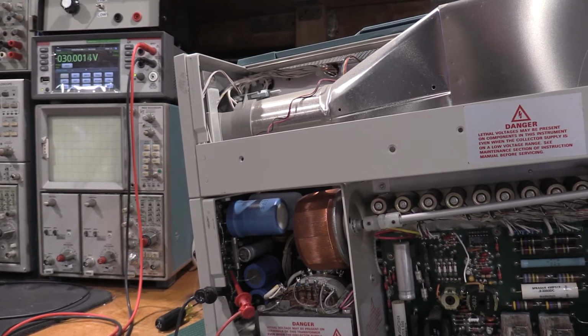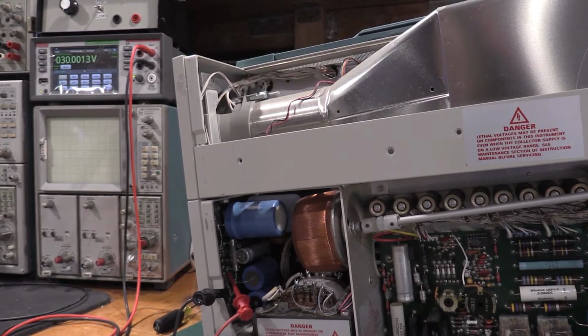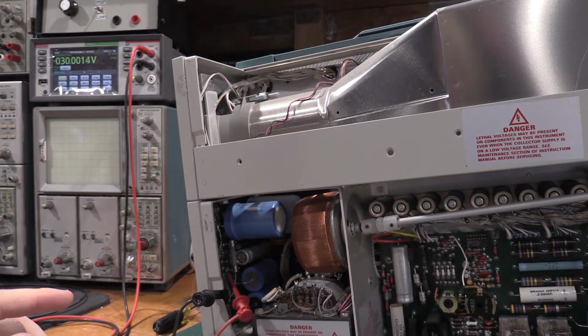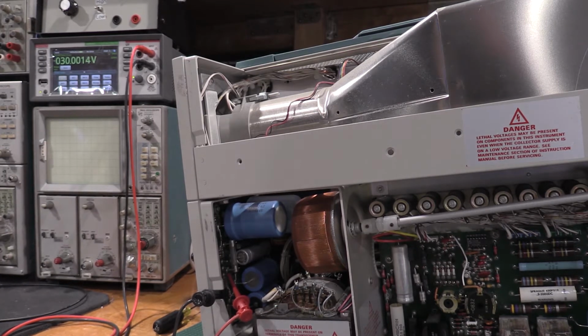Okay, before I did anything with the calibration, I did want to check the plus 30, minus 30 volt power rails, and it does turn out those were out of spec. So I did adjust those, which does mean we're going to need to do a full recal of the instrument because the power supply rails were toast. So I'm in for a full cal, but that was to be expected anyway. They're in spec now, 30.001.